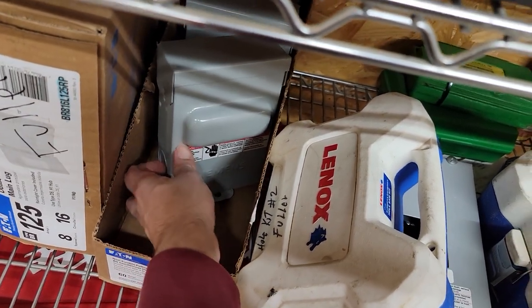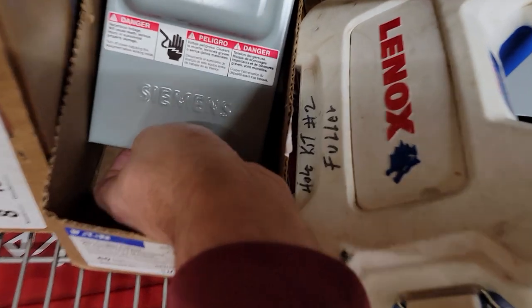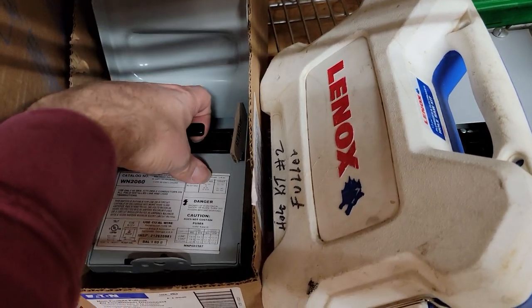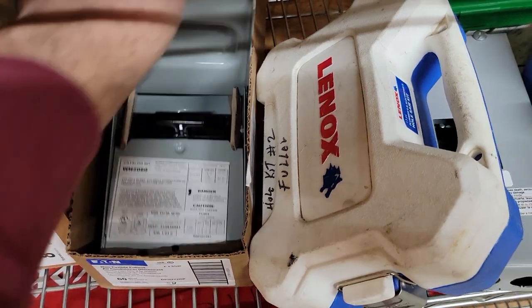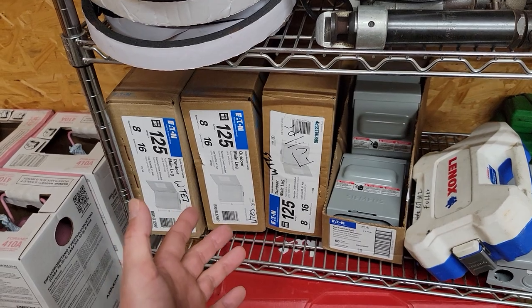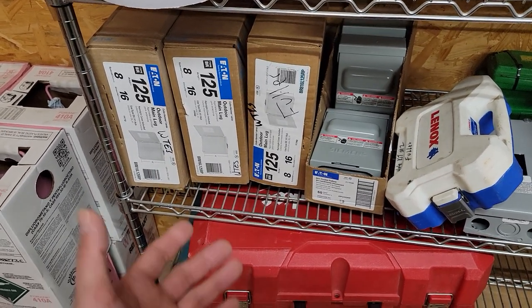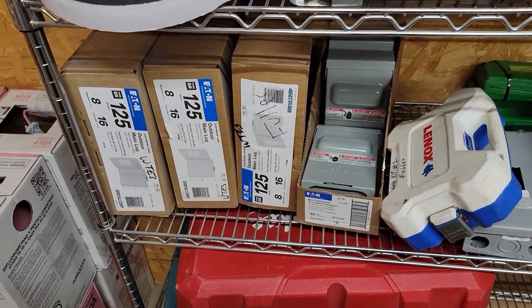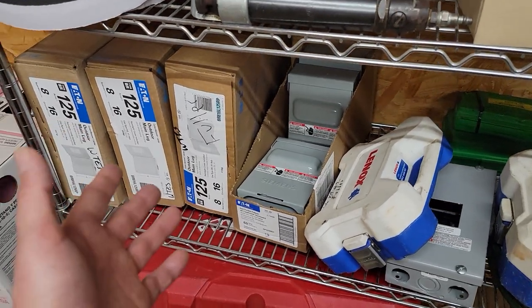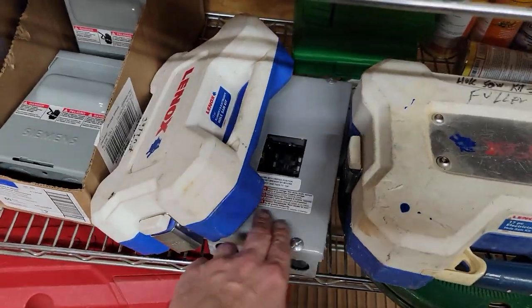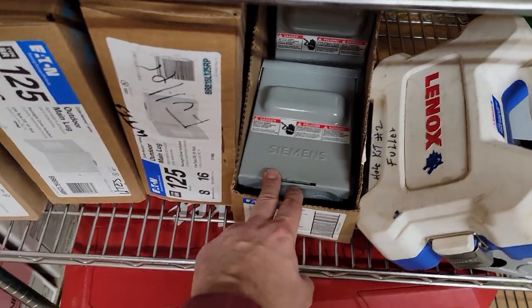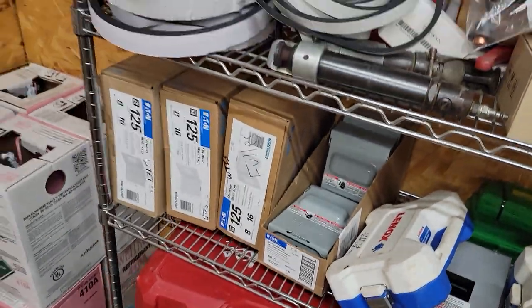This is a 60 amp disconnect, and this is something that has to be replaced summer or winter, doesn't matter. Got the parts you pull out there. That's something that has to be replaced, and sometimes the bars will rust out. Sometimes they'll be melted because of heat and a loose connection. That's something you have to have. This is an indoor disconnect here, and this is an outdoor disconnect. Know the difference. You got to know the difference.